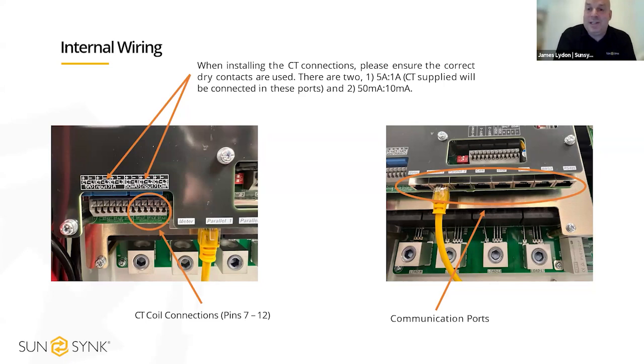So the image on the right, you can see we've got the parallel lead that will then go into the inverter next to it, into the parallel input. We've also got our CAN communications, so that's back to the battery. And again, on the left-hand side of the yellow cable, you can see there, that's for our meter if you are using the digital Eastron meter.